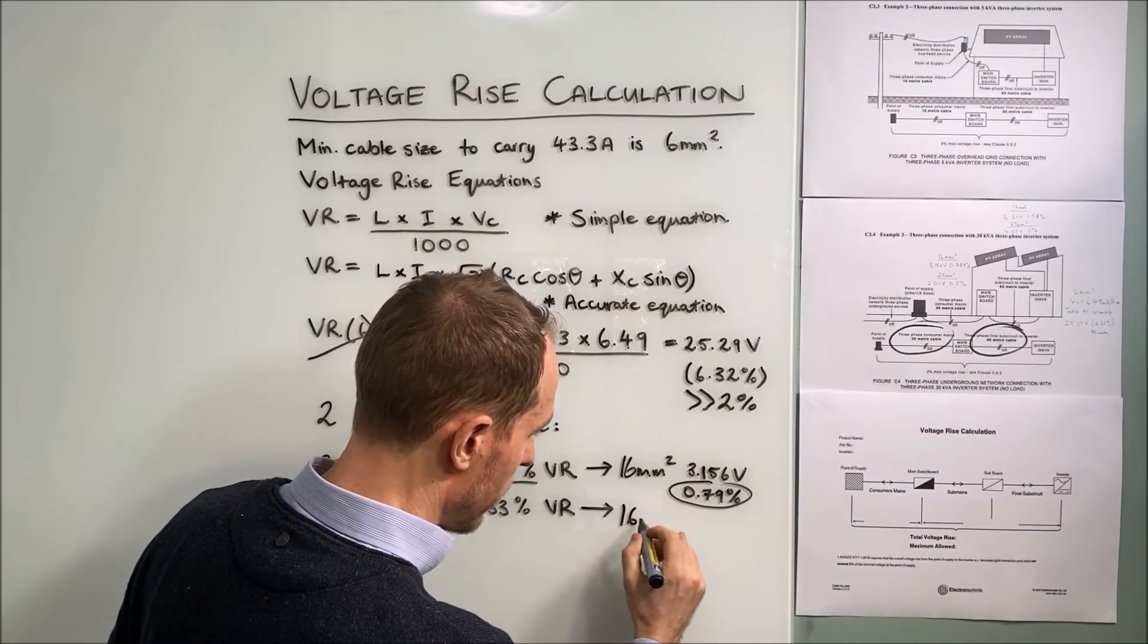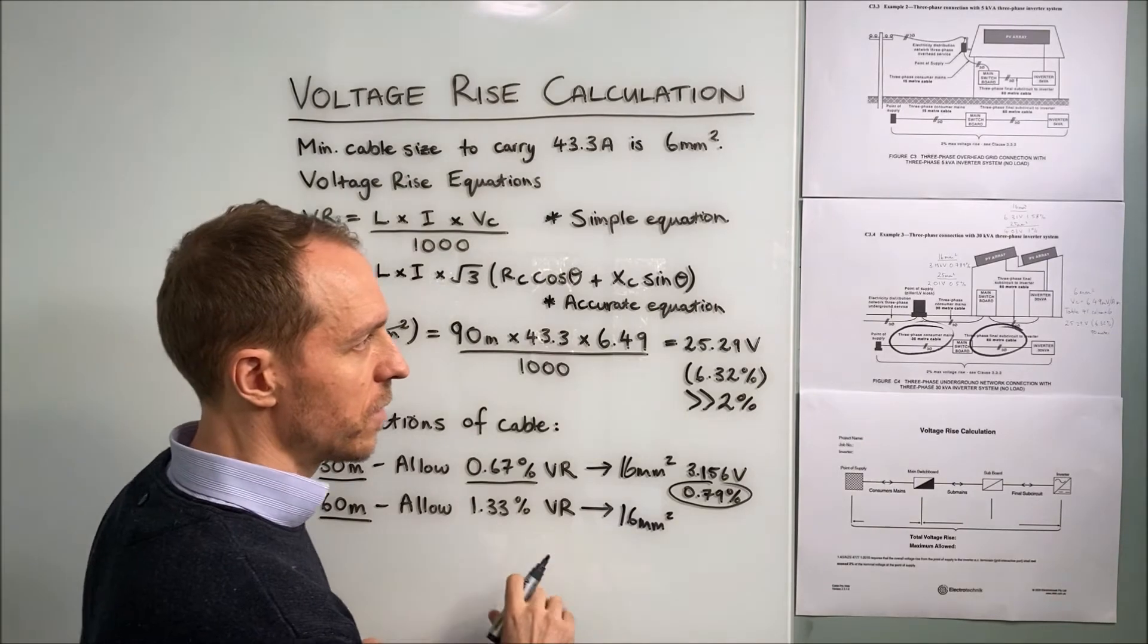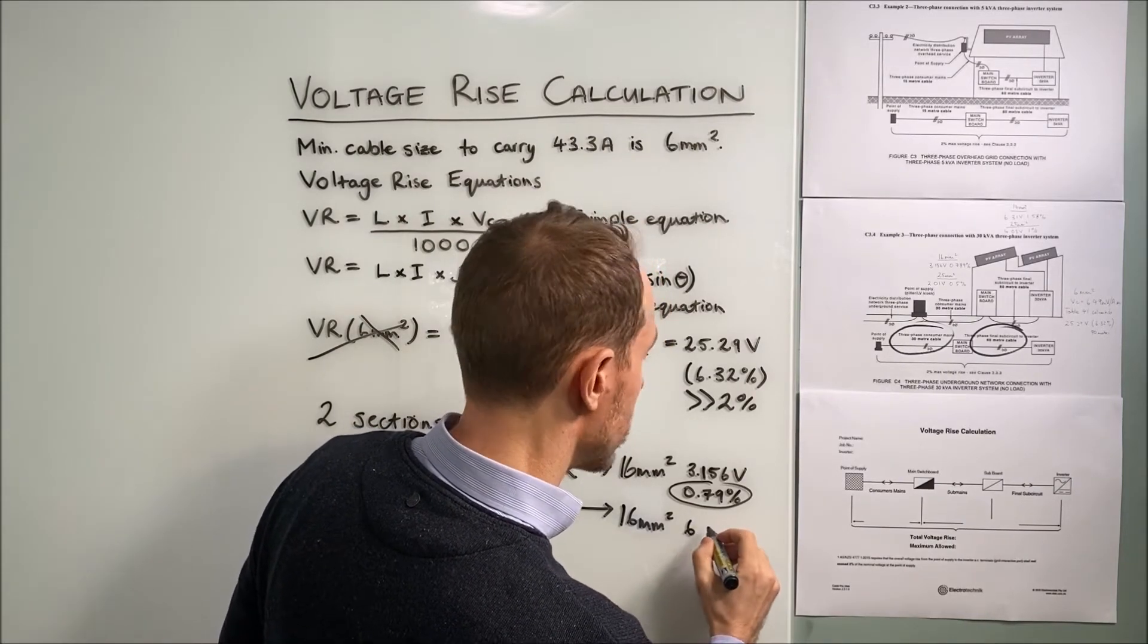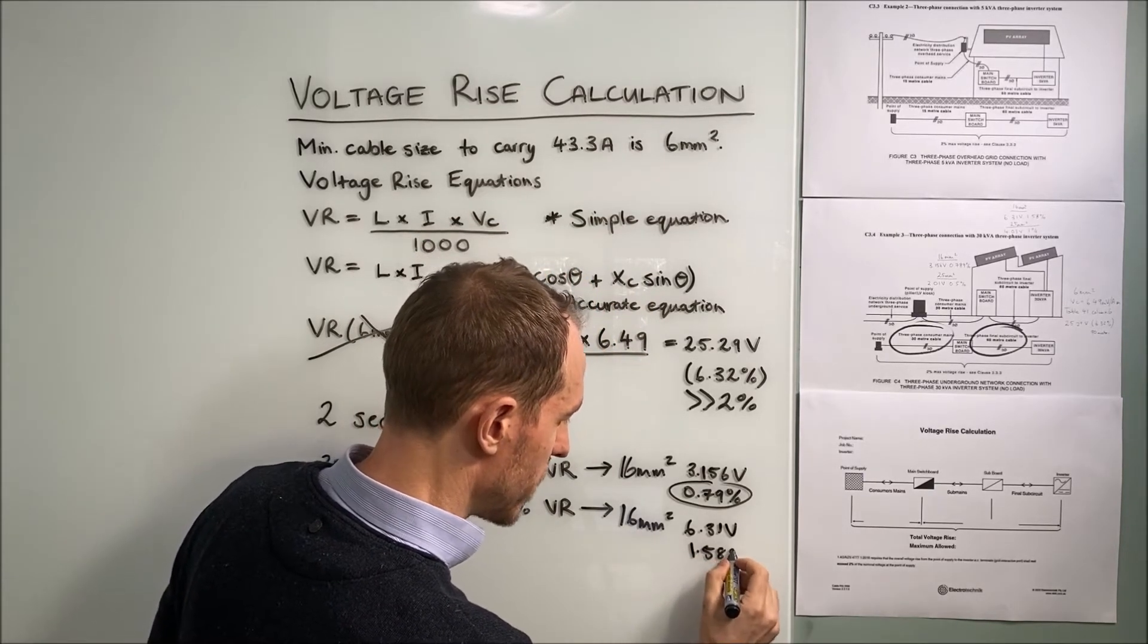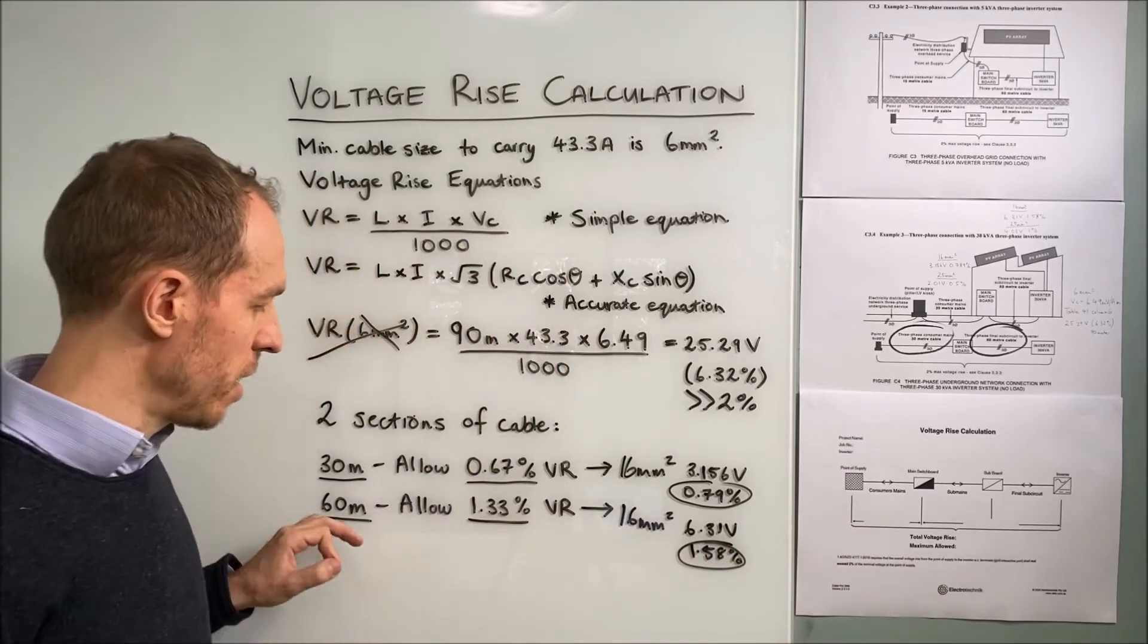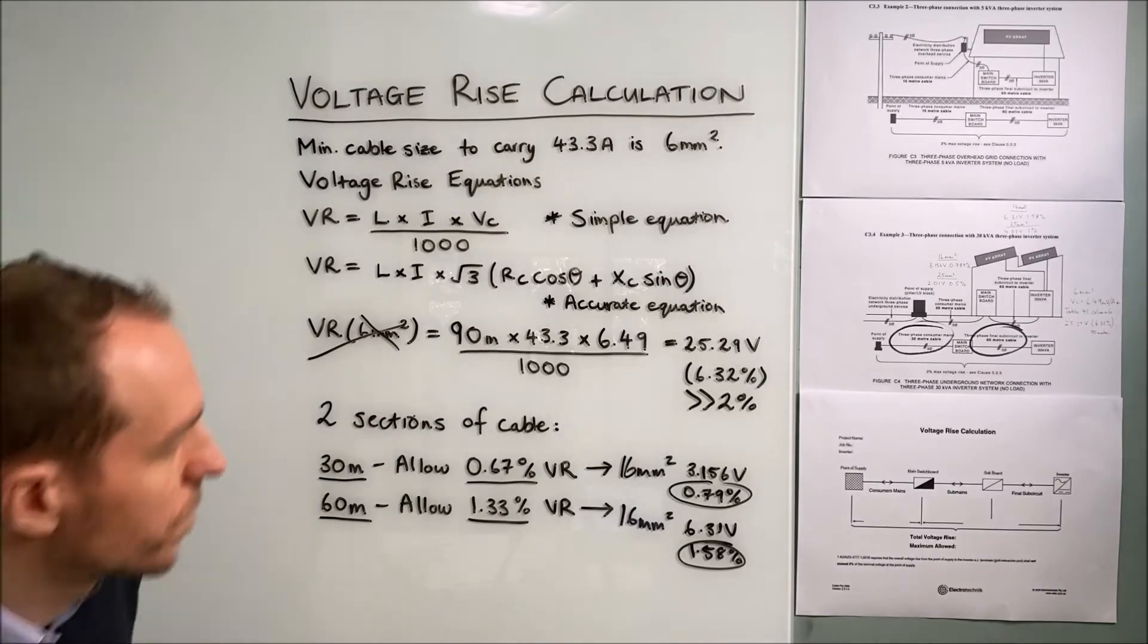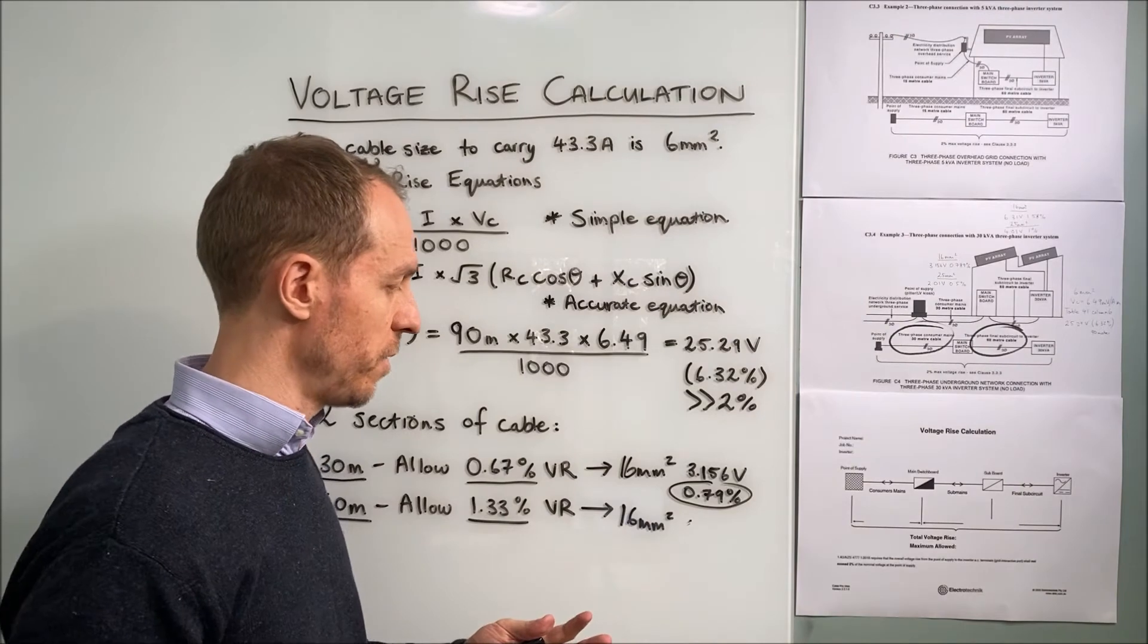16 square millimeter cable voltage rise for the 60 meter section. We calculated the result by hand to be 6.31 volts or 1.58% which is larger than our allowable limit of 1.33%. I'll move to the next cable size up and we'll see if we meet our requirement.